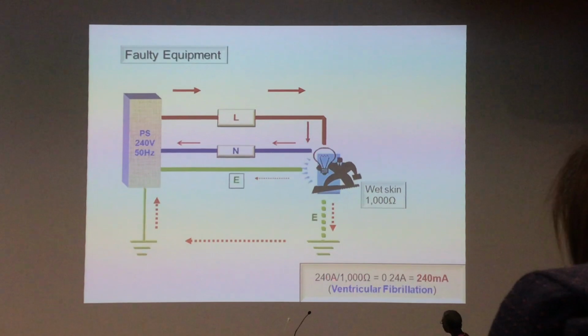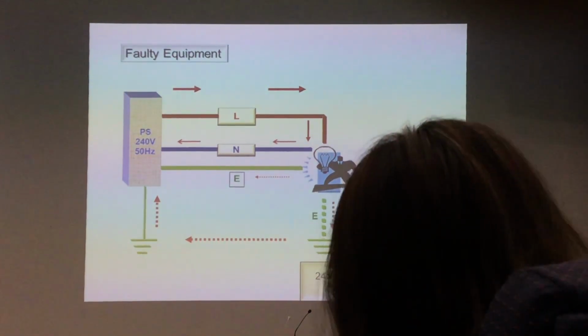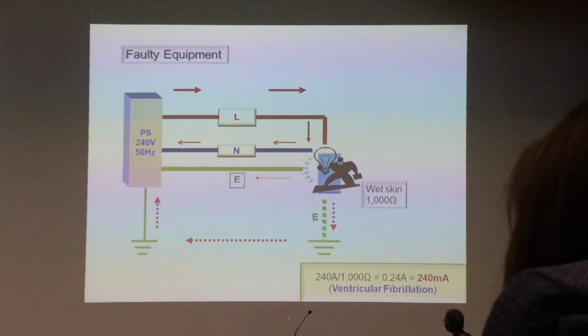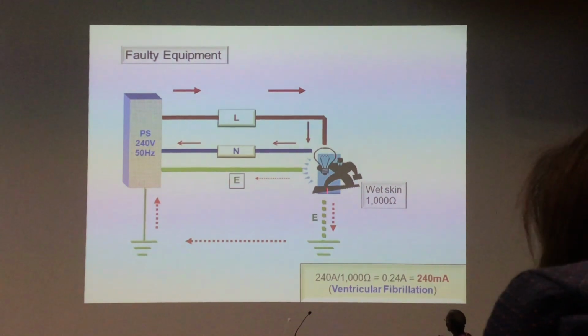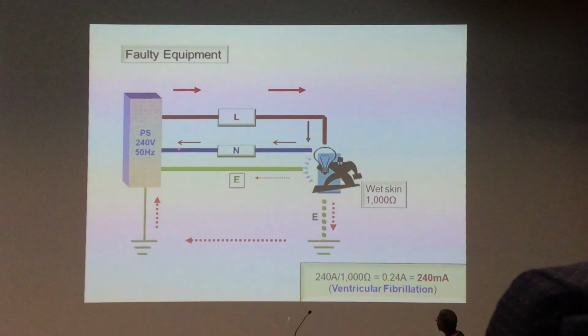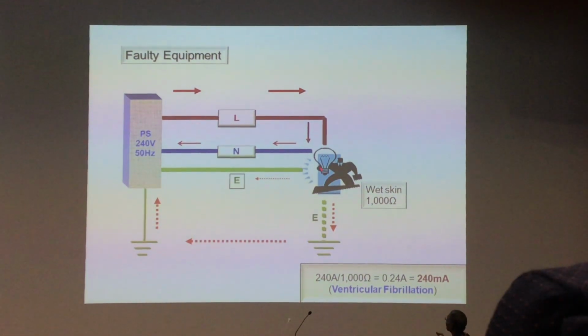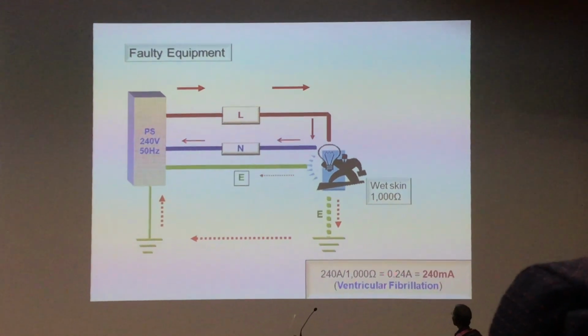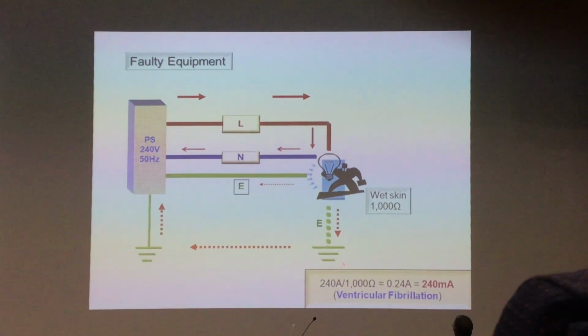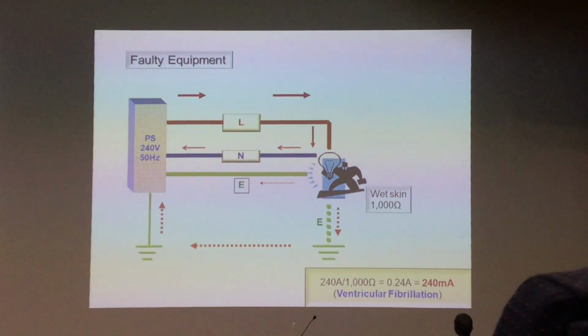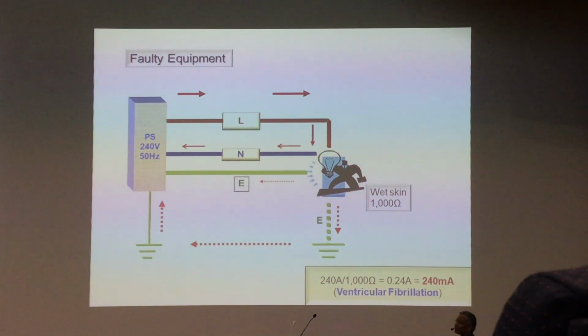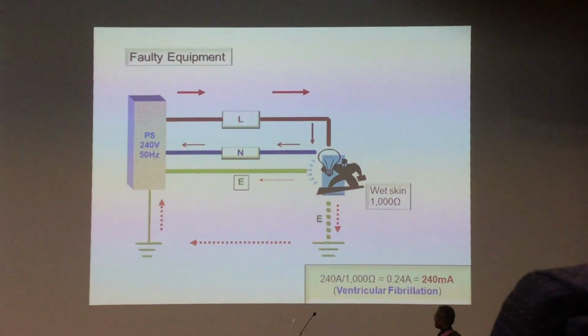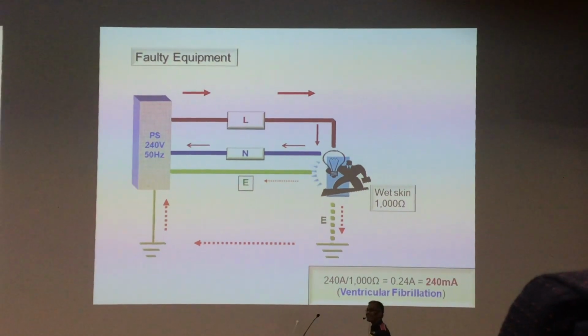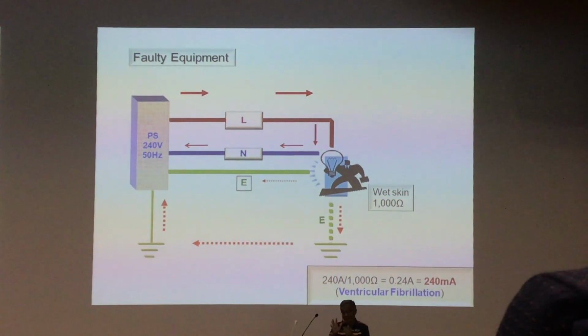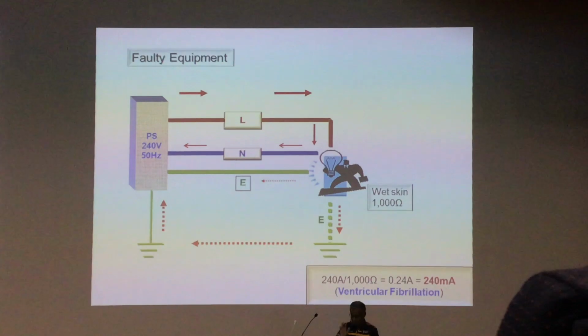This is the 240 milliamp. You have wet hands, low resistance. The current does not return through the neutral but goes through your body, because your body has very low resistance. This amount of current passing through your body, 240 milliamp, is good enough to cause VF. So you go like that. So be careful. That's why you make sure your hands are dry when you handle the machine.